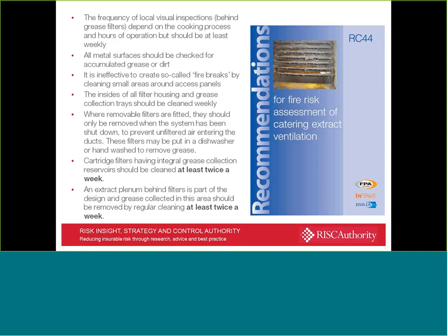RC44 provides a bit more detailed guidance. It says the frequency of local inspections behind filters depends on the cooking process and hours of operation, but should be at least weekly. So that's just for a visual inspection. Metal surfaces should be checked for accumulated grease or dirt. It also advises that it's ineffective to create fire breaks by cleaning small areas around access panels in order that potentially the fire won't spread from one space to another.